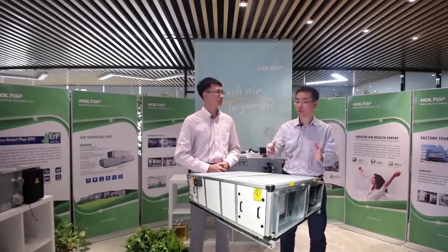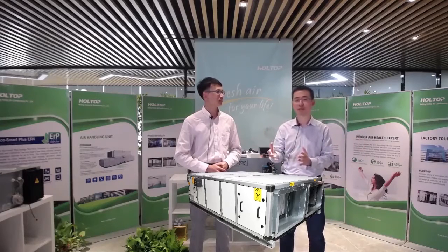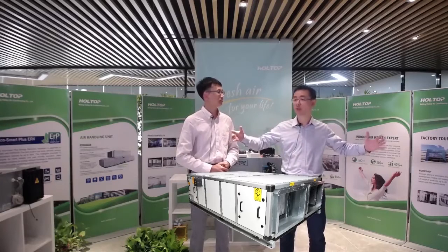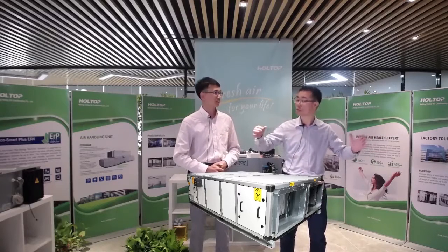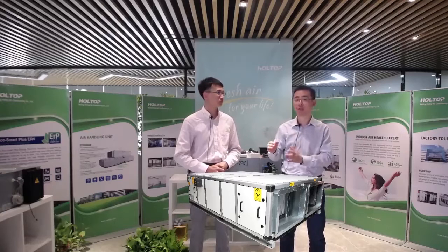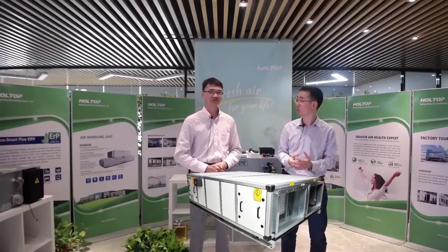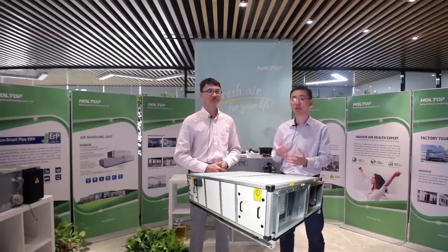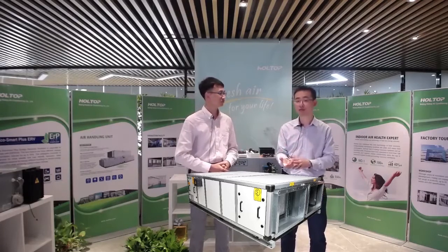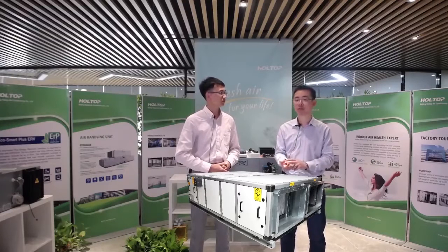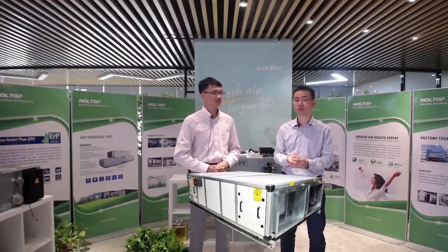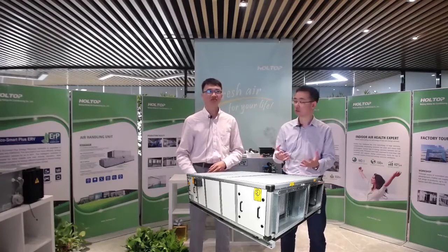And what's more, some offices have a very long size, so a long distance of ducting is needed to distribute air to each corner of the room. So it requires high external static pressure. And our units can be 100, 150, 250, and 300 Pa to meet the requirement. So that is to say, our unit is a very good solution for the office.